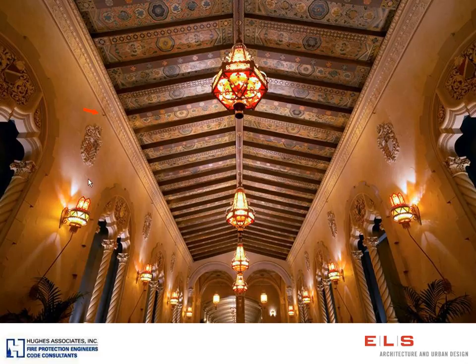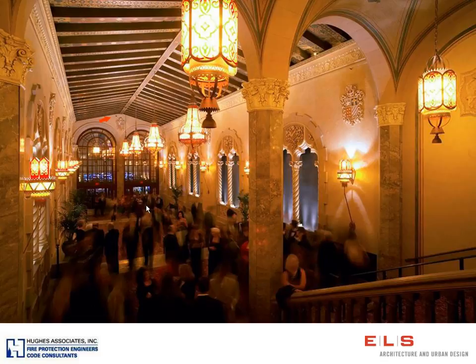On the walls, there were cavities behind the walls where we could run the piping, and the plaster, though it had a decorative finish, was fairly plain, and it is something that we actually could replicate in the restoration process. So anyway, we put the sprinklers in, and in addition to that, we also put in a beam detector system, as Cheryl described previously, and that beam detector system is mounted up tight to the ceiling.